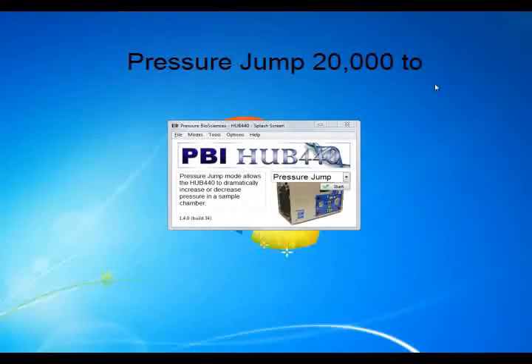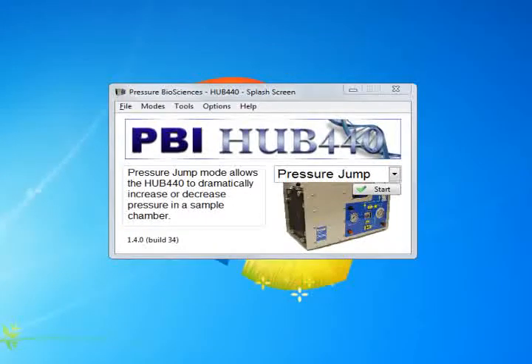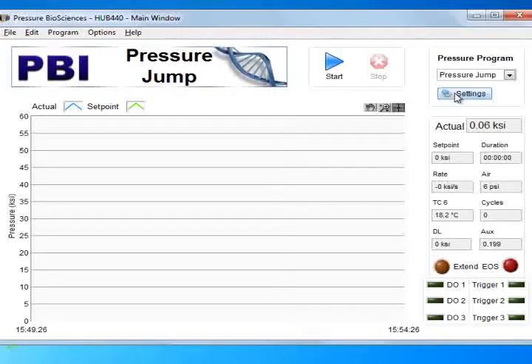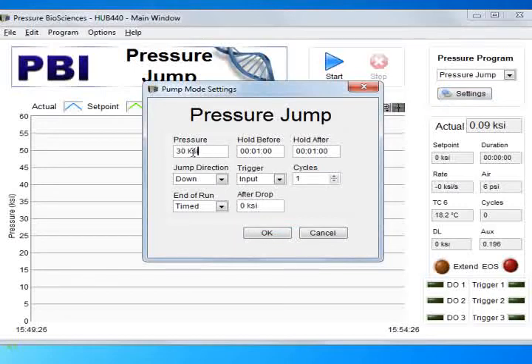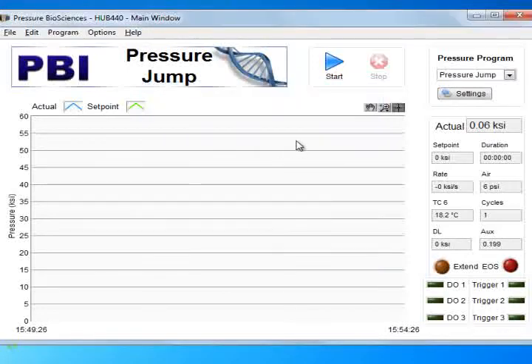The pressure jump option is employing rapid valves to facilitate changes in pressure of several thousand psi just under a millisecond. This approach may be invaluable for a variety of applications such as rapid kinetic measurements of high-pressure effects on enzymes and cultured bacteria to material stress and testing of various components and assemblies for leaks under rapid pressure changes. In this example, we are going to show you the pressure jump down from 20,000 psi to 5,000 psi.